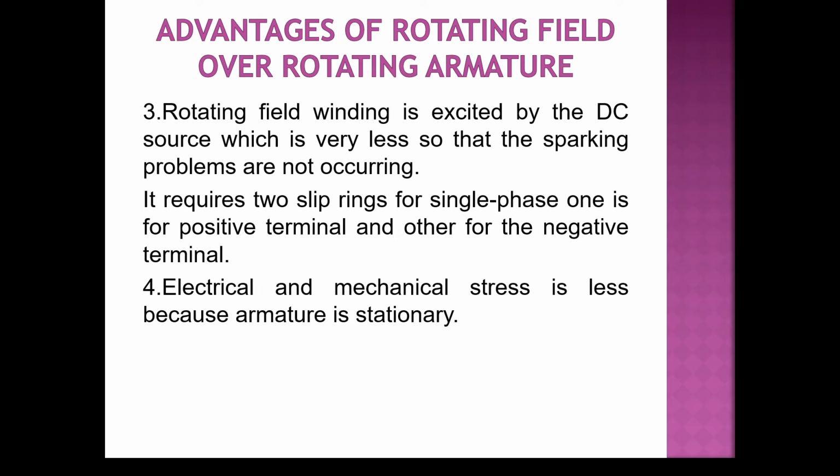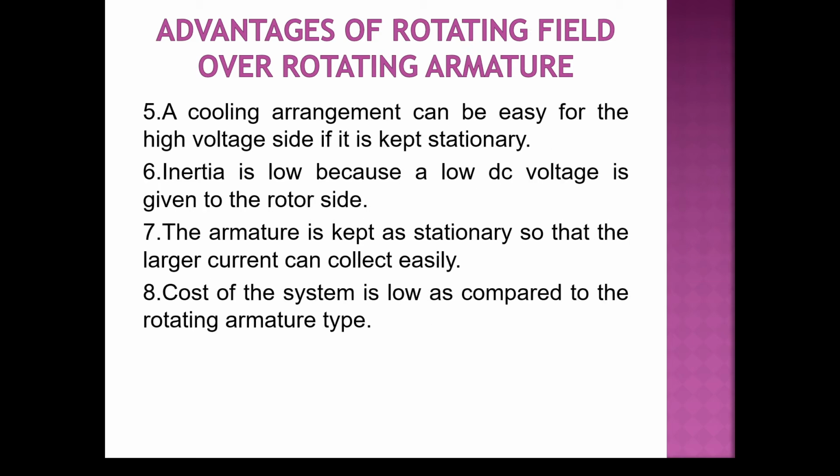As the armature is stationary, electrical and mechanical stresses will become less now. When the armature was rotating, there were mechanical losses, friction and windage losses. Now those losses are reduced because the armature is stationary. And one more advantage of rotating field is that the cooling arrangement can be easy for the high voltage side if it is kept stationary. So cooling arrangement can be easier now.